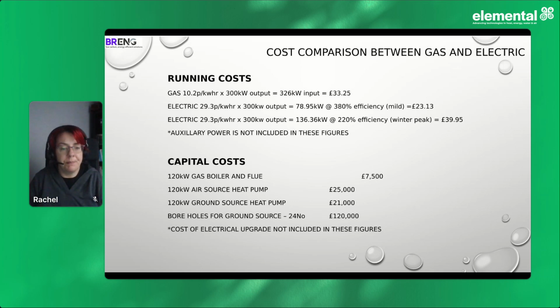If we compare typical running costs: a gas boiler with a 300 kilowatt output would cost about £33 an hour to run at full output. If you converted that to an air to water heat pump running at its most efficient, in mild conditions, designed and sized properly, your running costs will actually be lower than the gas boiler, based on its efficiency and the tariff. But if you don't use the heat pump properly and the efficiency drops, it will in fact cost you more to run. That's why it's important to ensure that when air to water technology is applied to a school, it's done correctly, otherwise it will cost a lot more to run.